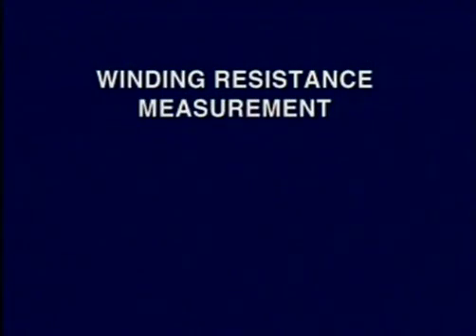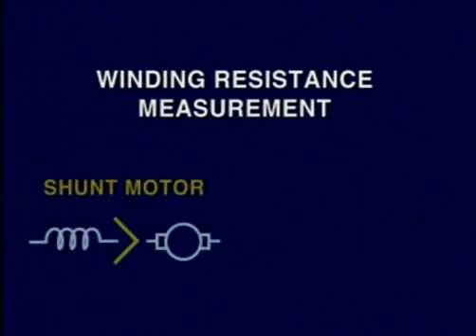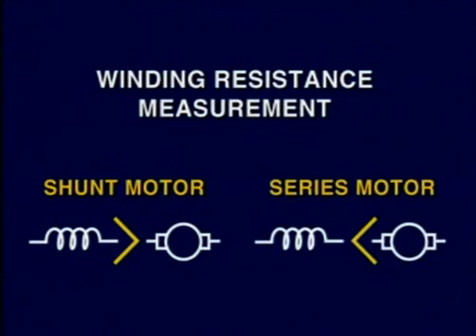Note that when taking a resistance reading in a shunt motor, the shunt field winding resistance will be much larger than the armature resistance. Conversely, in a series DC motor, the series field winding resistance will be less than the armature winding, since the series field is made of large gauge wire. This small detail will help you identify which wire belongs to which winding in a DC motor.